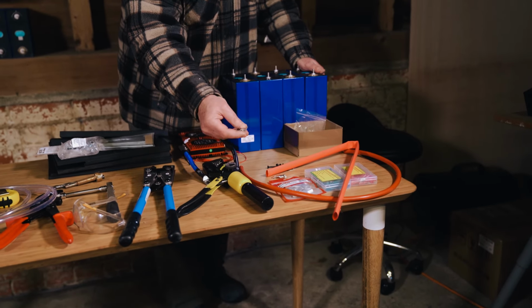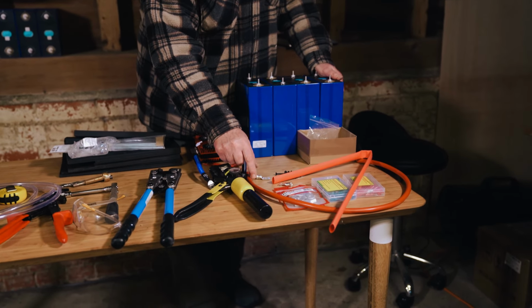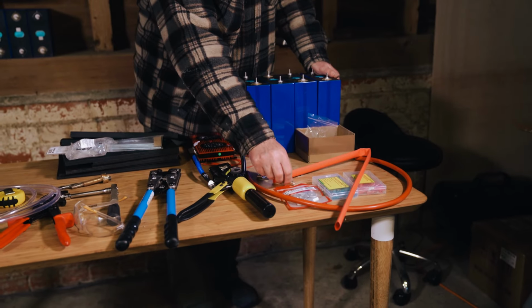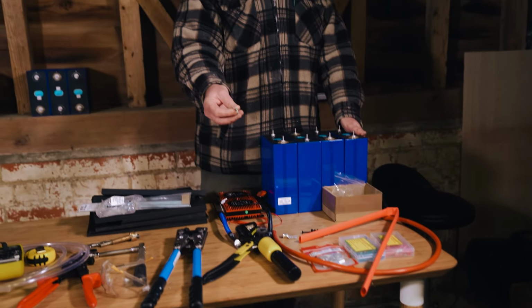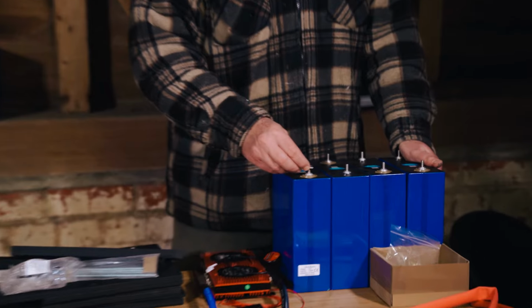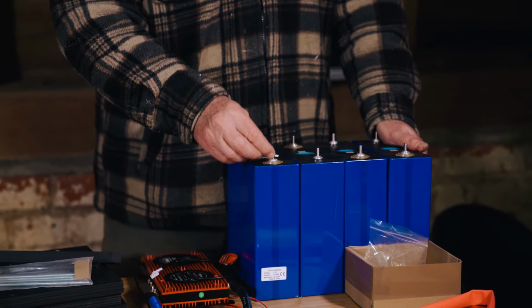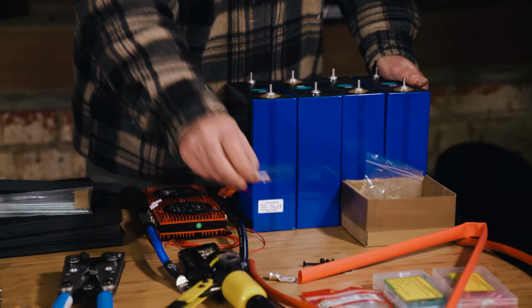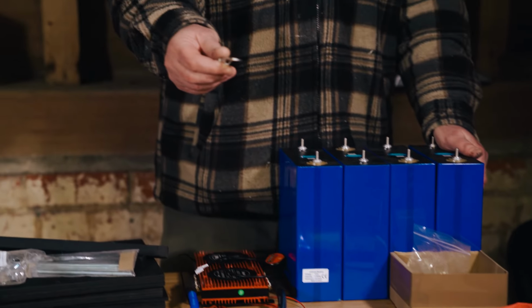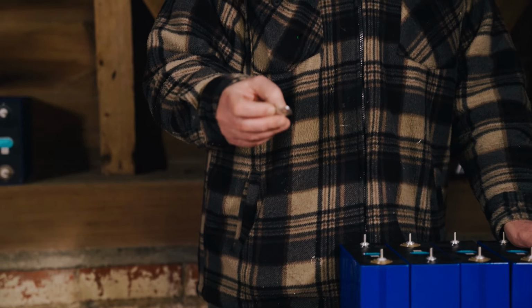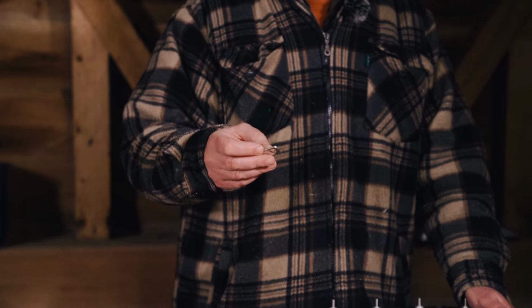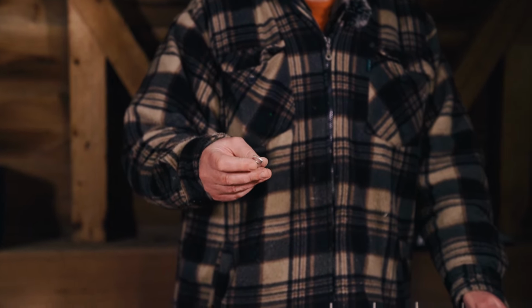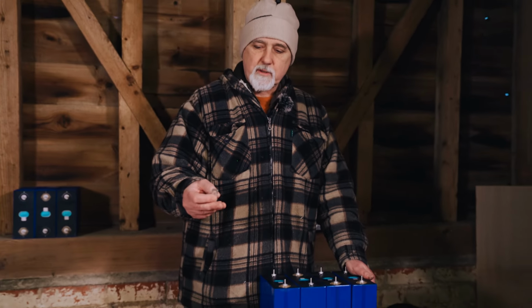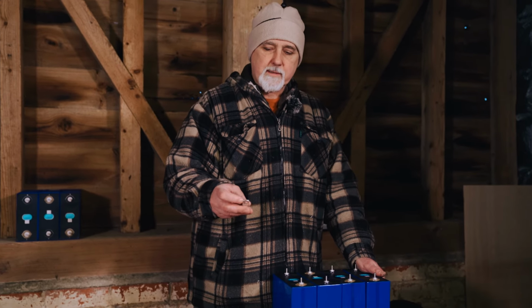You want 2 lugs to terminate the two ends of this red cable. So you're going to want at least a 6 millimeter lug, which fits over your terminals quite nicely. The other lug will depend on where it's going. If you're going, for example, to a Victron smart shunt, an 8mm is not enough - you need a 10mm lug on the other side. So it all depends where you're terminating as to what size lug you're going to get.